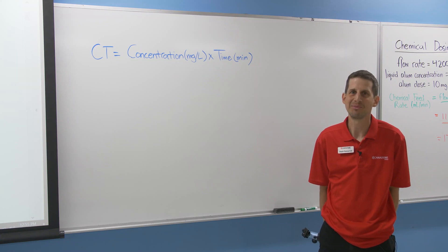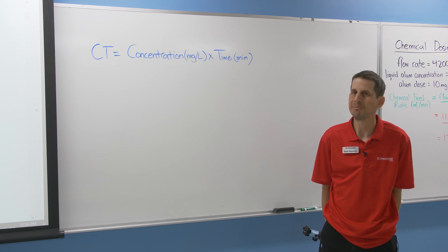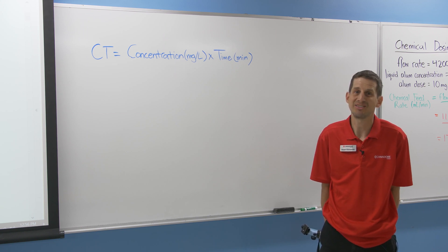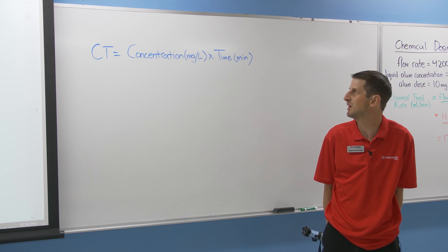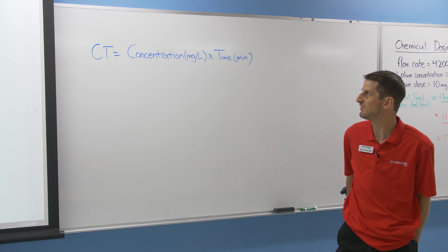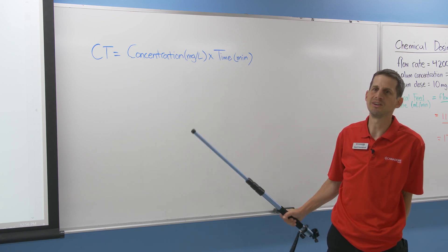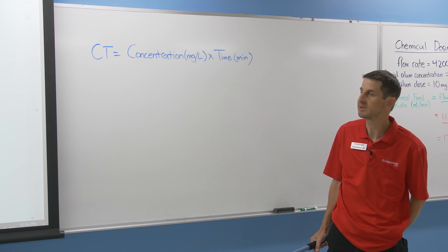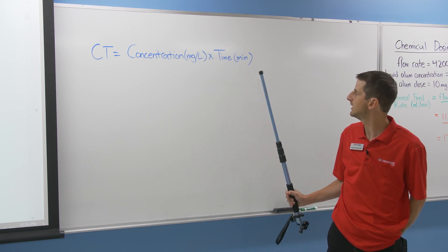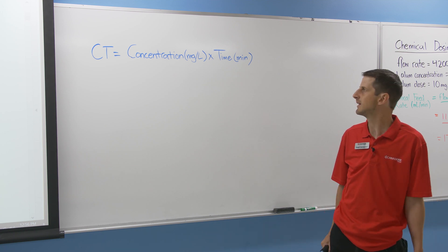We've got another challenging concept in water treatment called the CT concept, which baffles some operators. But really the CT is kind of neat because it's got its own definition. C stands for concentration, T stands for time. There's a value called the CT value, and you calculate it by multiplying the concentration of your disinfectant — chlorine disinfectant residual or other disinfectant — and multiply it by the amount of minutes you're going to have it in the clear well getting disinfected.